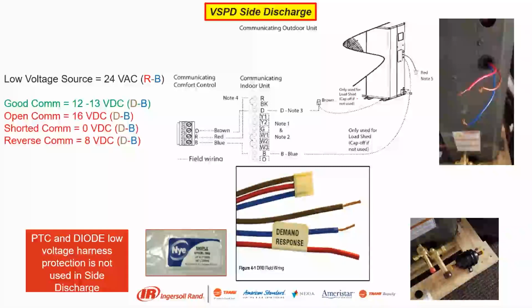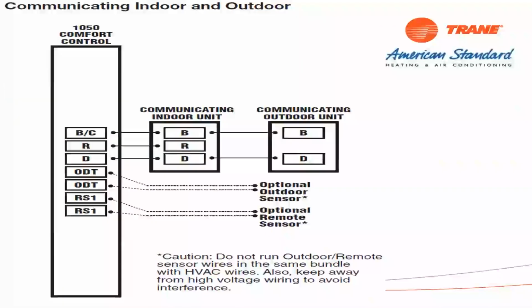This is a good slide that shows good communication between brown and blue, the data and the blue, data in common. It's going to be 12 to 13 volts DC when everything's connected. It'll show 16 volts DC if it's open, if it's not connected, or if it's connected and we have a short in the wire. Here's a shorted comm, 0 volts. So this is a good slide that we send out a lot to guys calling in for communication diagnostics. I mean, it's pretty straightforward.